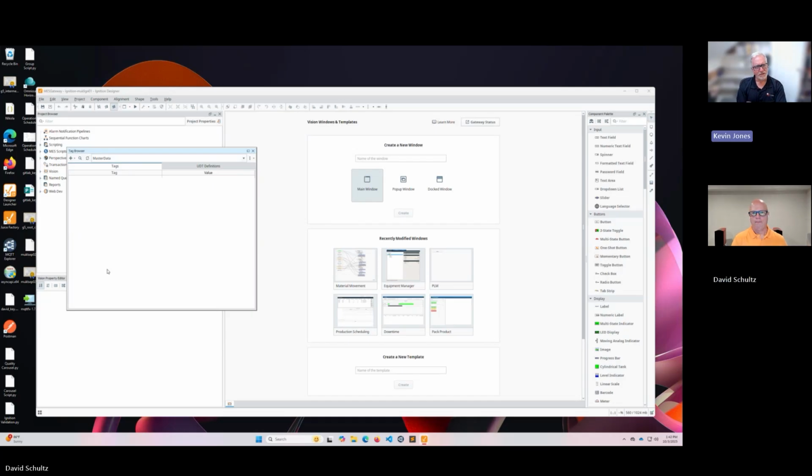A good example of that is a plant we were working with that had a bunch of CNC machines, 2 OEMs, and multiple models for each OEM. We had a core CNC model. Then we inherited from that to create the 2 different core models, if you will, for the 2 different OEMs. Then all of the models from there each had slightly different arrangements for tags, so we inherited from that to create those UDTs as well. But there was that core, literally and figuratively, that central CNC model we started with, which had all of the very basic tags that a CNC should have in that shop, at least.